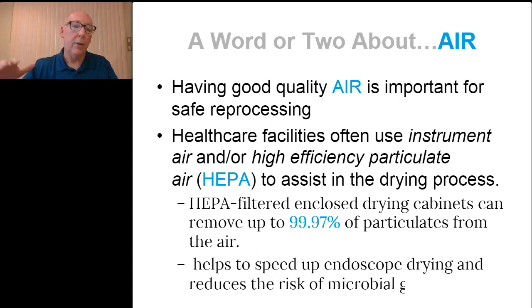So that air is first coming through that pre-filter, filtering out all those large particulates before it goes into the HEPA filter. Sometimes those filters need to be changed once a month, twice a month, etc., but they're there to work for you. So pay attention to where they're located, take a look at your drying cabinet IFU, and replace accordingly. Make sure you have enough air filters on hand so you can replace them when you need to.